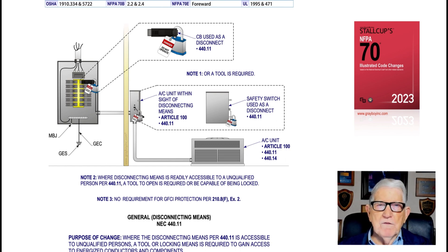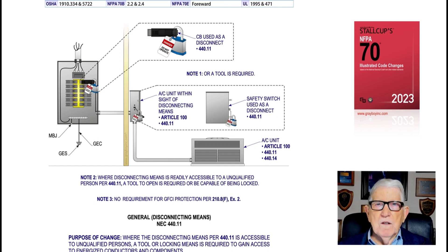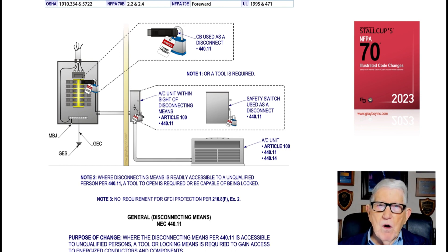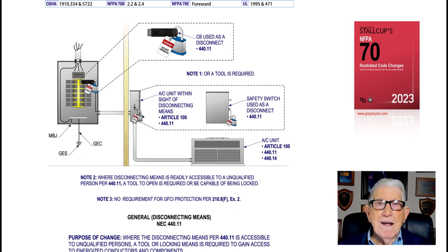Just a lock — not a tag — would be required, or a special tool. Also worth noting: GFCI protection of the circuitry to an AC unit is not required by Exception 2 to 210.8(F), which is on approximately page 81 of the NEC.